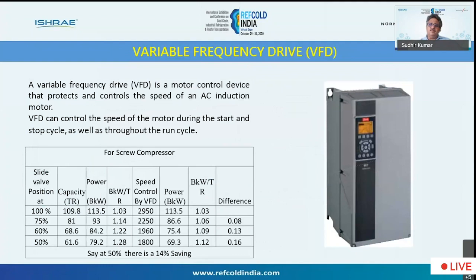After coming to compressors, then we have discussed motors. The next major part where you can save on power is the VFD. VFD is nothing but a variable frequency drive, where you are able to control the speed of the motor to reduce the capacity of the refrigeration system. So by using a slide valve, also you can reduce the capacity.